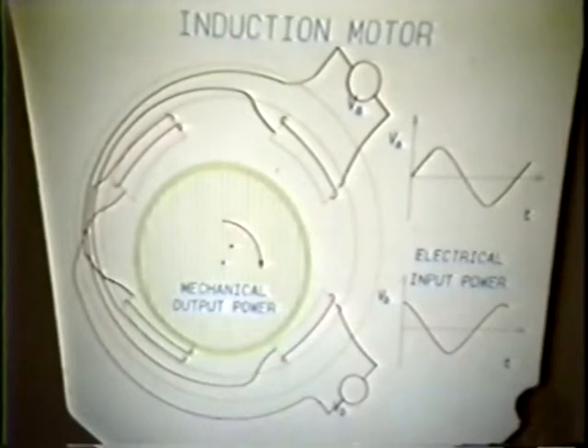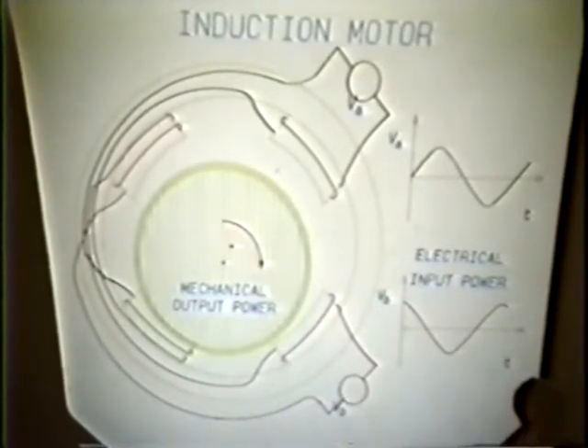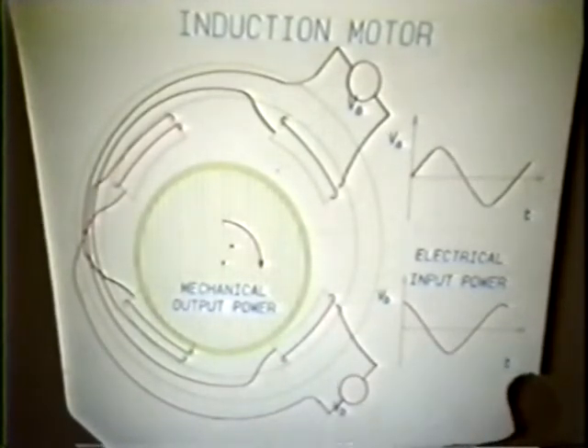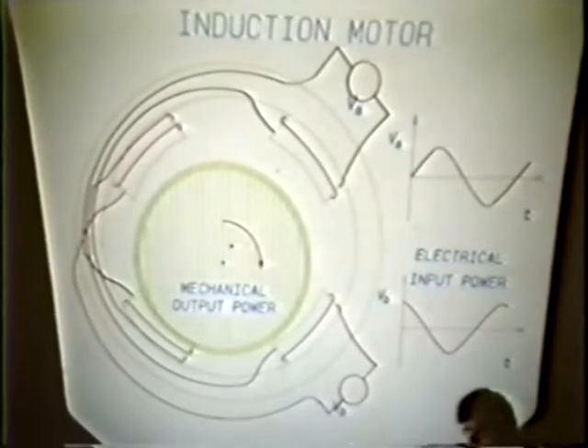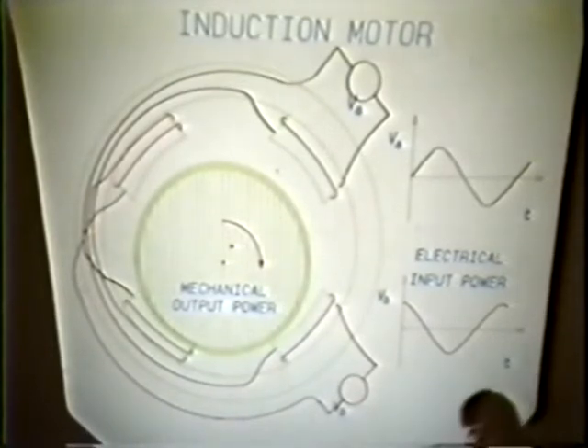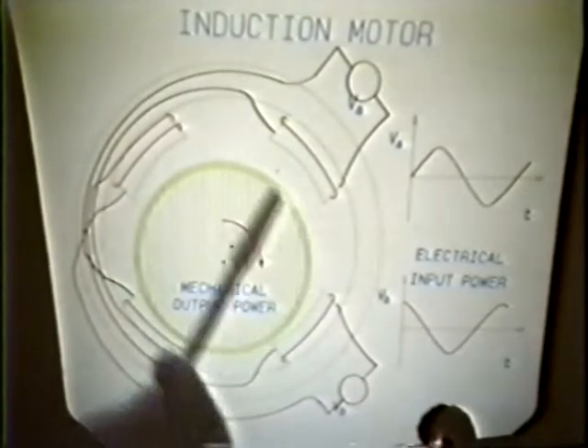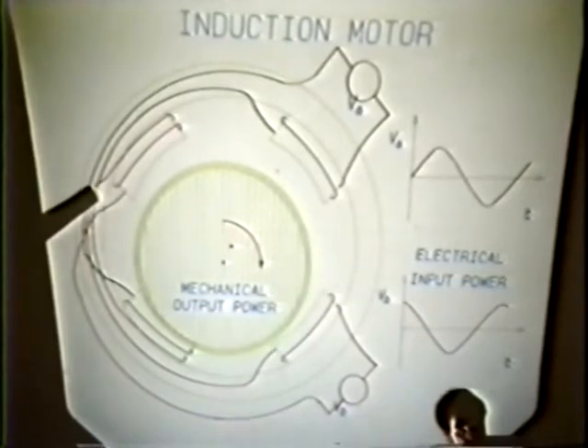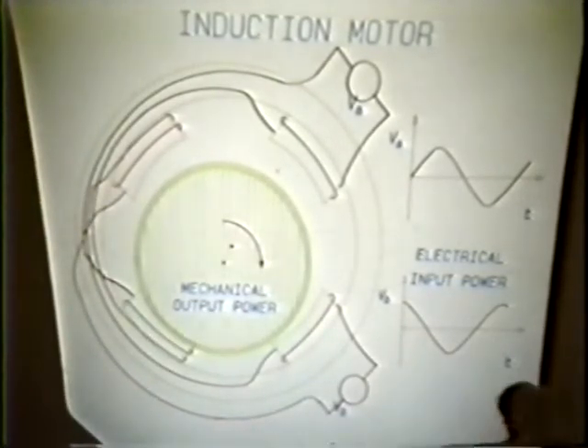In fact, you obtain an induction motor, which is featured by the fact that it cannot operate at synchronous speed, which we just mentioned is 3,600 RPM for 60 hertz operation, but it operates slightly below, behind it, with a so-called slip frequency or slip, typically slip maybe one percent or so. So for 3,600 RPM, maybe your actual physical rotational speed of the rotor is 3,500, 3,550 RPMs or so. So by making this induction motor, he was able to create the ideal device which completely eliminated all the mechanical connections. There is no mechanical connections needed to bring the power to the rotor because that was obtained by transformer action induced from the primary winding into the secondary.